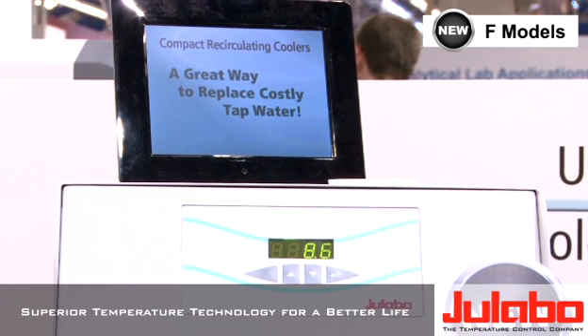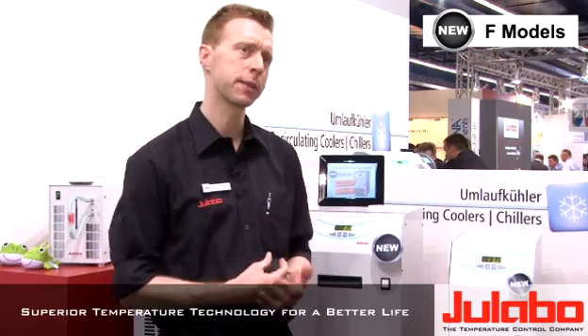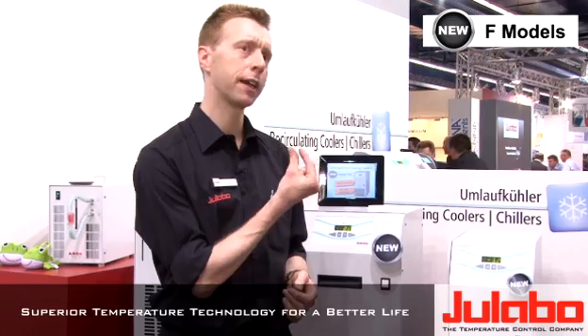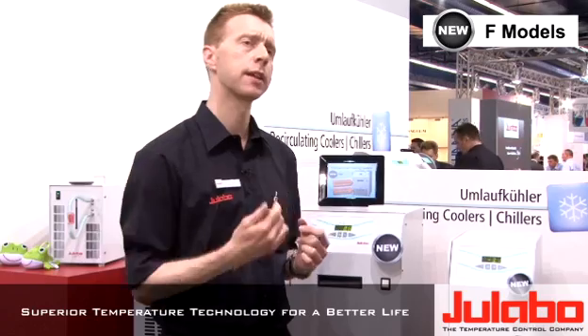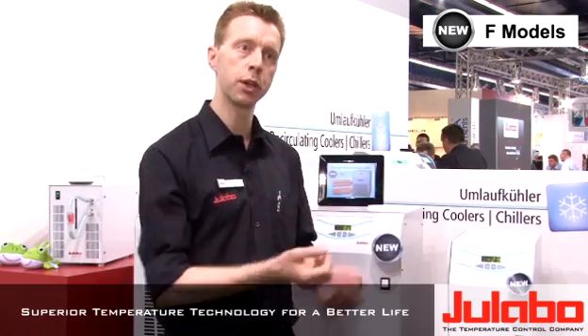Another feature is the way we do the heat exchange. A lot of manufacturers use so-called plate heat exchangers — very compact but having very fine channels. What happens is these channels are easily blocked by minerals. At Julabo we thought we could do it better and give the units a longer lifetime. We're using a normal bath heat exchanger, the pump fully immersed, can never run dry. Lifetime up to 20 years.